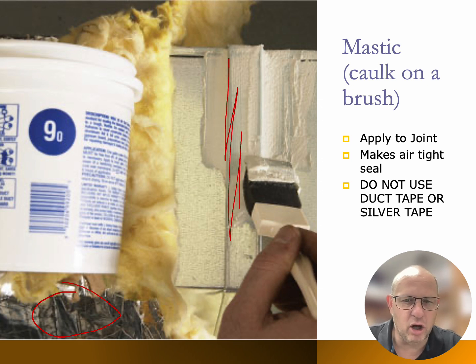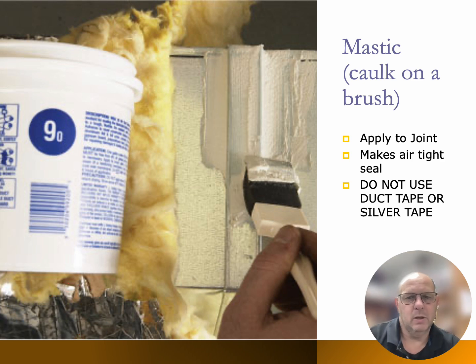Now you can see we call it caulk on a brush, yes, because we are painting that actual fitting with caulking from the mastic itself that's sitting there on that. Apply it to the joint, makes an airtight seal. Do not use duct tape, do not use silver tape, do not use any type of tape to seal up that particular air in there. The adhesive that is on that tape will not last over the course of that particular system.